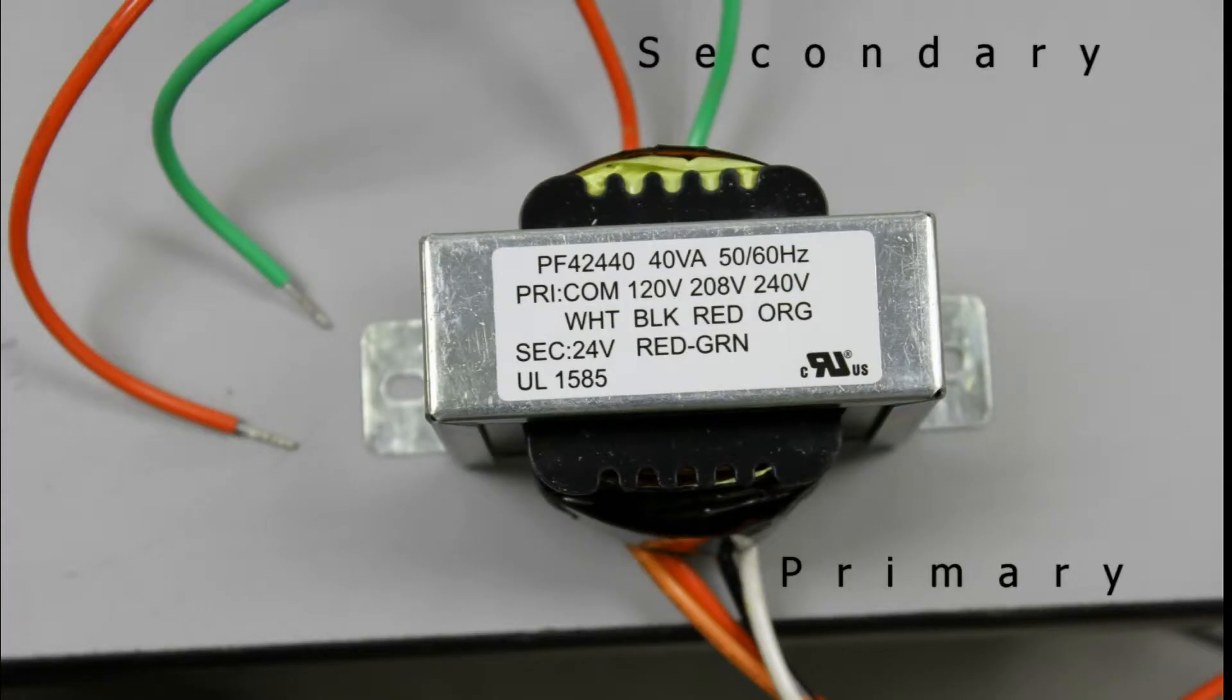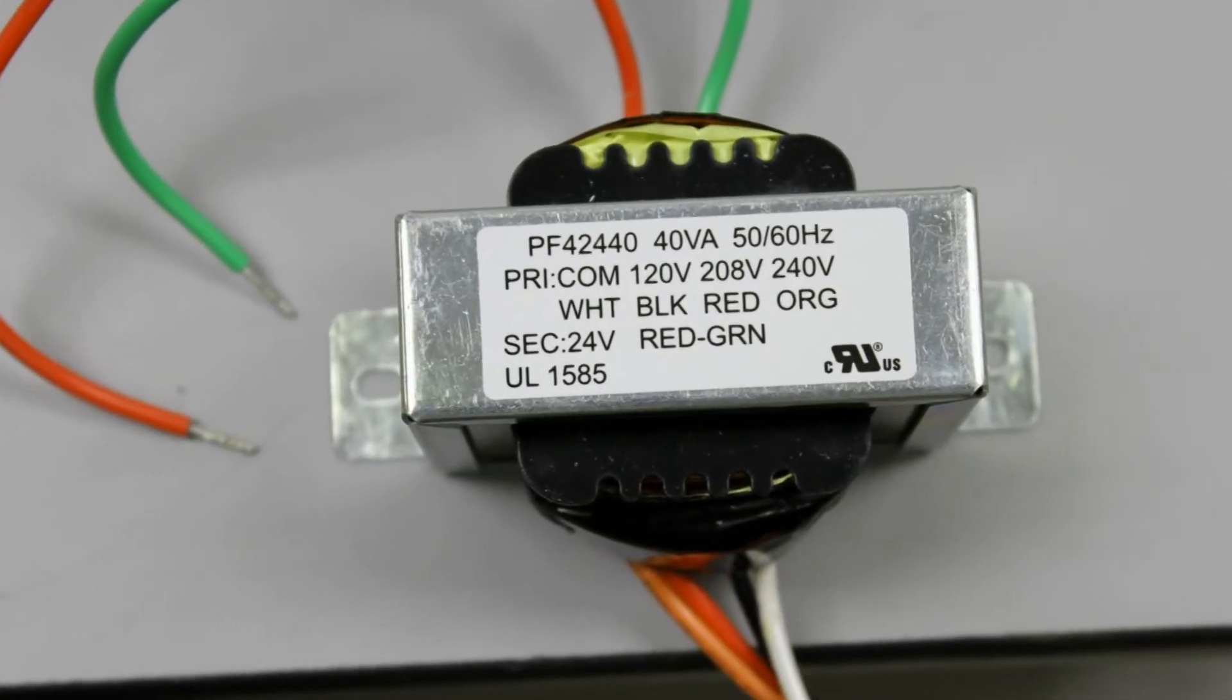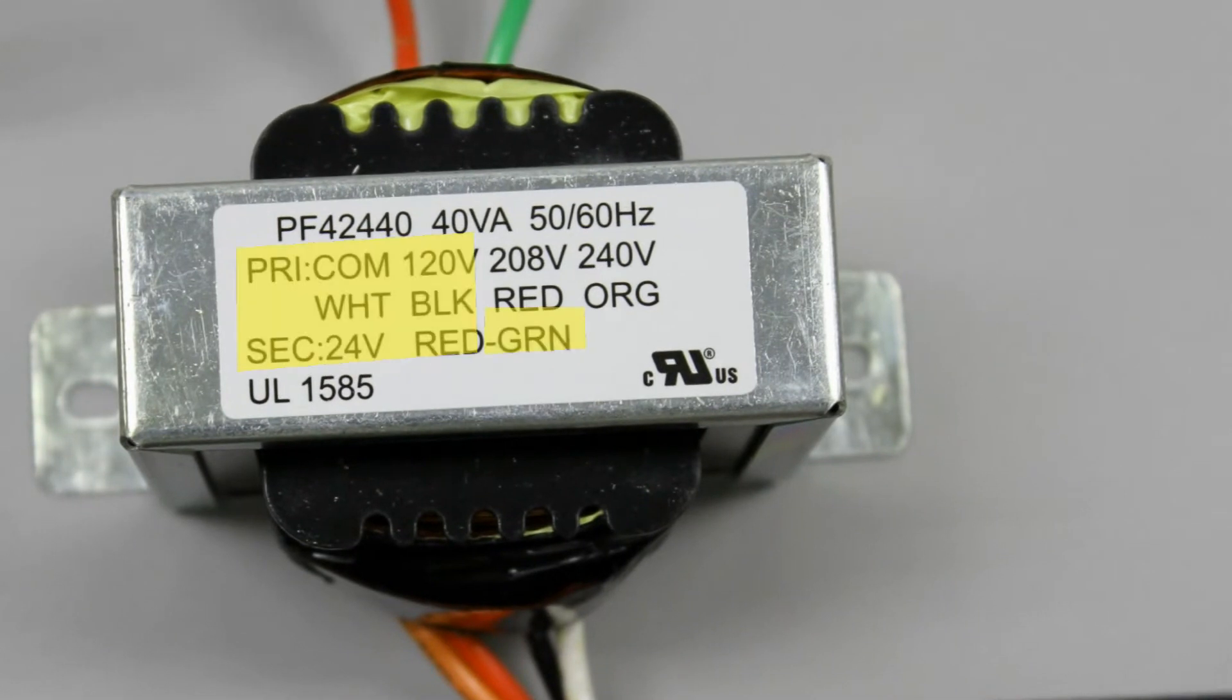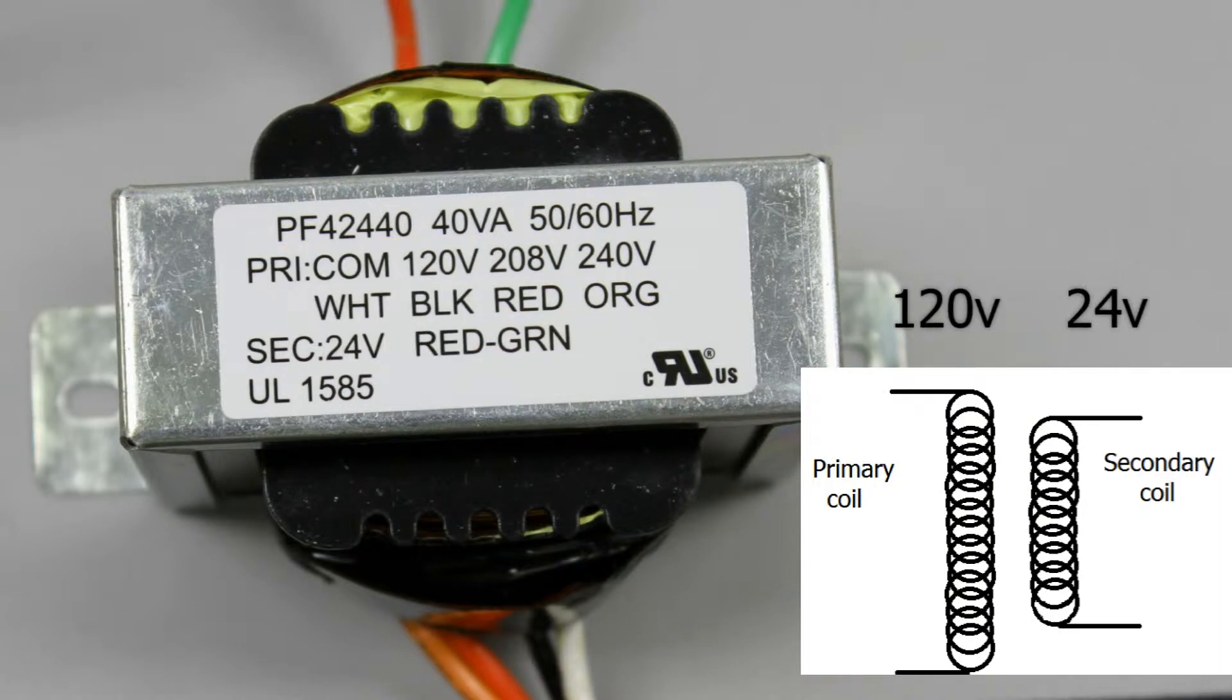Here we see a transformer. Secondary is at the top, primary is on the bottom. Transformers have a label. You'll notice it says 40 VA. Transformers are rated by the secondary volt amps, or power. Here you can see the primary and the secondary voltages. When we use the white and black on the primary, that's for 120 volts, and we'll get 24 volts out. That's a 5 to 1 ratio.